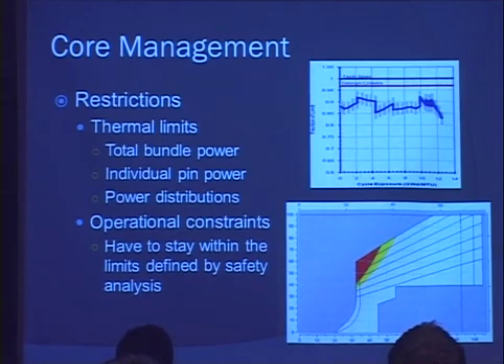You also have operational constraints, which you have to stay within the designs of your safety analysis. This right here is what we call a power and flow map, and anything inside the white region is where we're allowed to operate. Anything gray, we have no idea what happens there, so we don't operate there, and these are bad. Pretty much what happens is this is pump capacity this way, and this is core flow this way, so you want to maintain something that's nice in here.